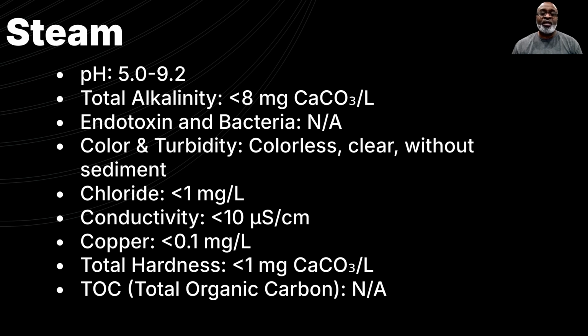Total hardness, less than 1 milligram per liter of calcium carbonate to reduce scaling and maintain sterilizer efficiency. Total organic carbon, TOC, is not applicable to steam. By adhering to these parameters, steam ensures safe and effective sterilization, supporting both compliance with ST108 and optimal patient safety.